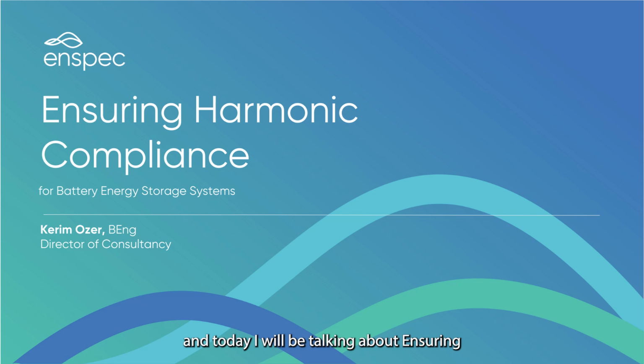And today I will be talking about ensuring harmonic compliance for battery energy storage systems. I will be mainly focusing on a real site case study. Basically, I will be demonstrating the results without harmonic filter and with a designed, manufactured, and commissioned harmonic filter for a real 33 kV connected 50 megawatt BESS site in the UK.